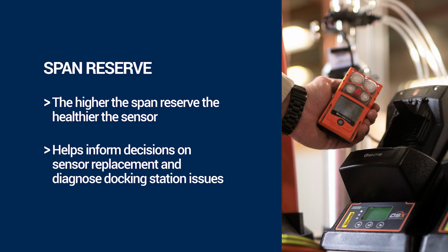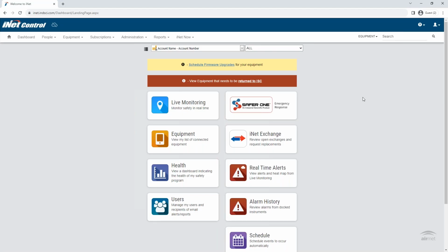All sensors have a span reserve. Think of it as the health of a sensor. The higher the span reserve, the healthier the sensor. The span reserve tends to fluctuate throughout the life of the sensor, so iNet Control collates this data over time to help you make an informed decision on replacing the sensor or to help you potentially diagnose problems with docking stations. In this video, I will check the health of a methane sensor on a Ventis Pro5 instrument.